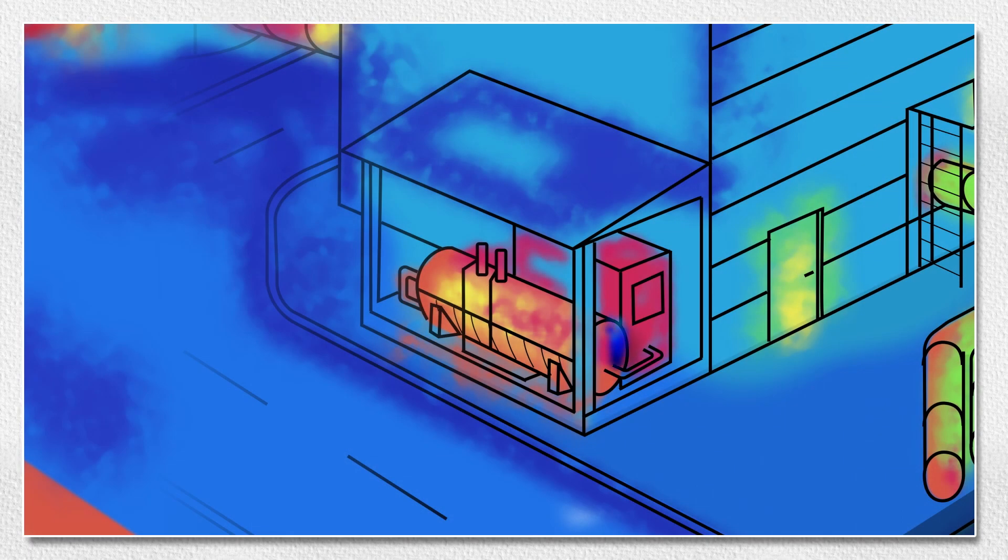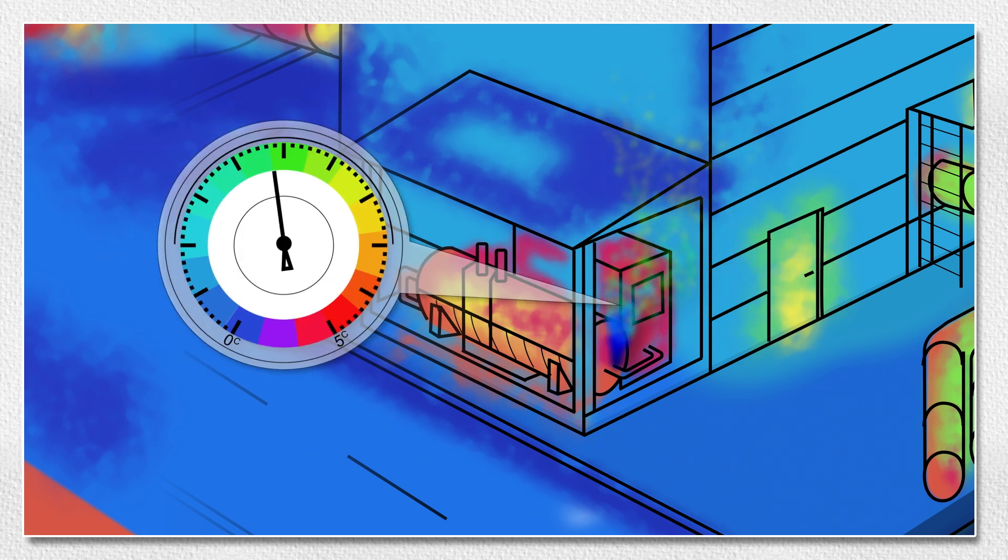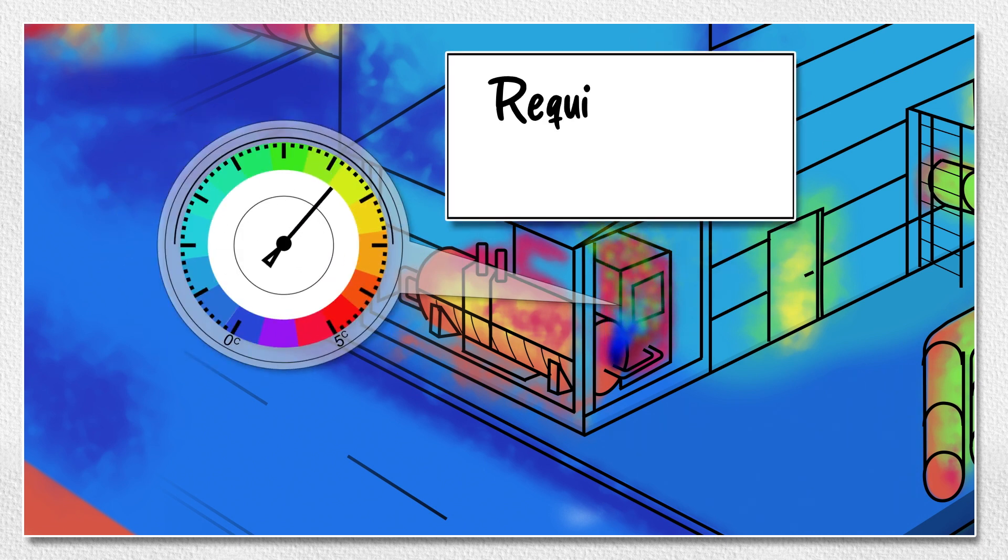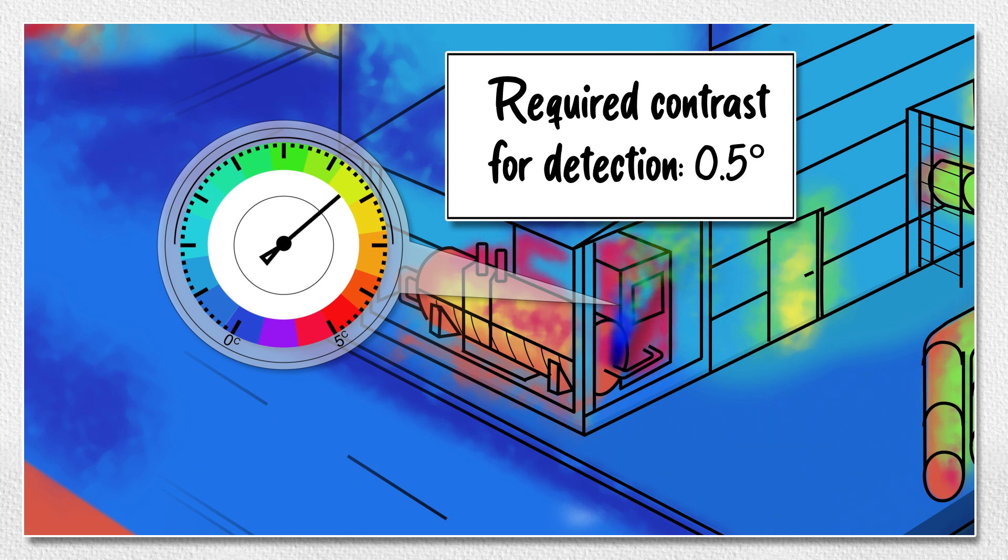When gas leaks, it quickly reaches temperature equilibrium with the surrounding ambient air. For an optical gas imager to detect a cloud, there needs to be a radiometric contrast of at least 0.5 degrees Celsius between the air and the background.